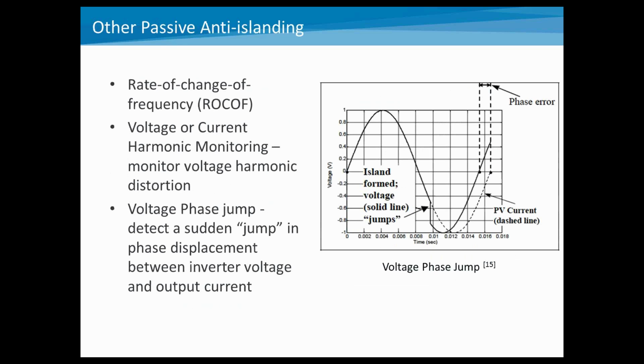Additional passive anti-islanding techniques include things like rate of change of frequency, looking at voltage or current harmonics, looking at things like a phase jump when all of a sudden an island is formed. Because you do typically have a load mismatch, you'll see that in the voltage or current outputs.